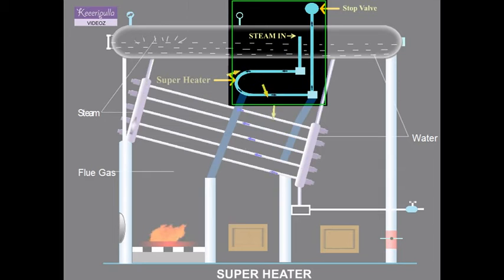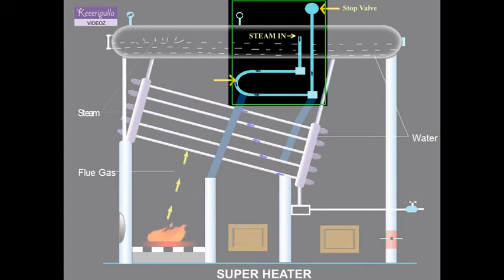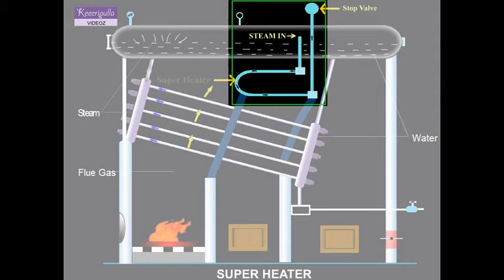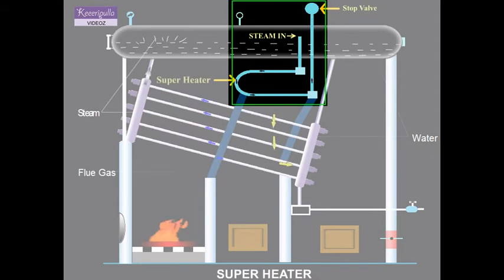The tubes are made of high quality steel in the form of U-tubes. The superheater is located in the path of furnace gases where the temperature of the gases is not less than 550 degrees centigrade.